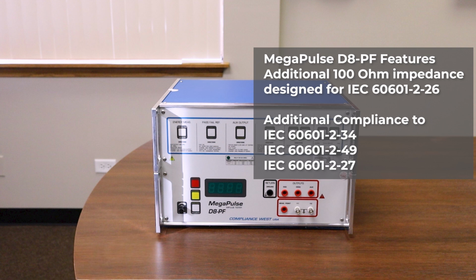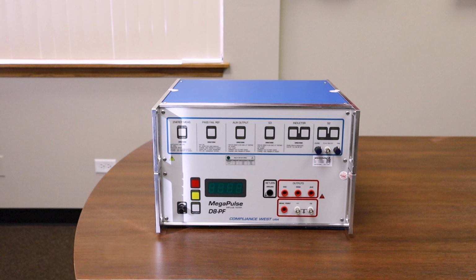This test system can also be used for testing to a variety of other requirements, including IEC 60601-2-34, IEC 60601-2-49, and IEC 60601-2-27, and many others. We have our D8-PF configured with options for the sine wave generator and HV jumper.